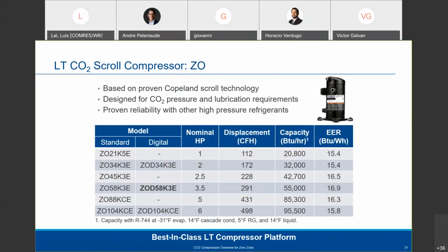So the scrolls themselves, like I mentioned, the first UL model was approved in 2009, been around, leveraging the shell of our 410A product line because they operate around the same pressures. From a nominal horsepower perspective, 1 to 6 horsepower, and we have 3 digital models, the 34, the 58, and the 104. And again, these capacities that we're showing here are at -31 Fahrenheit and 14 degree condensing with a 14 degree liquid. So to give you an idea, look how high the EERs are. The EERs are very high because compression ratios are quite low on CO2 compressors. So that gets factored into the overall system COP.